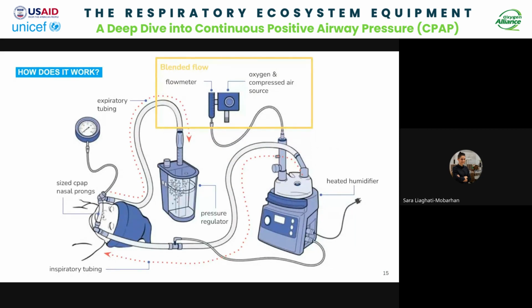So some CPAPs will have an internal pressure regulator, and this ensures that this happens at the same pressure. Some will only have a Y connector with no additional pressure regulation. And that means that for each product, it's important to look at the specifications for the device to make sure that the oxygen source that you're using is appropriate for your specific CPAP device.